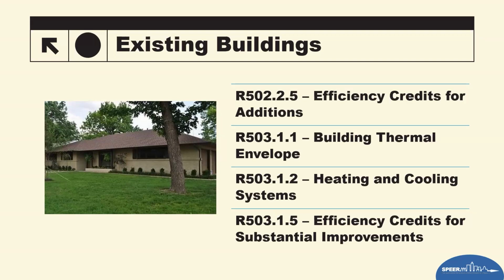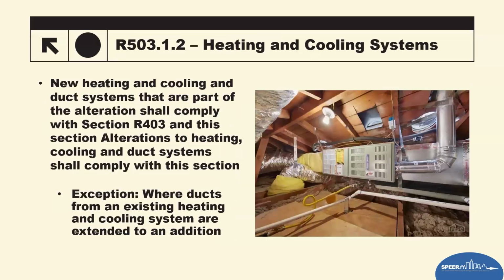As we said earlier, that's now defined in the definitions, but it will also be up to a building official or the AHJ to say what is a substantial improvement and whether I now need to enforce the code, as it's not just a repair but something that needs to meet new code requirements. So with this, new heating and cooling duct systems that are part of the alteration shall comply with R403, which is now sizing of the equipment and following Manual D duct design. Alterations in heating and cooling must also comply.